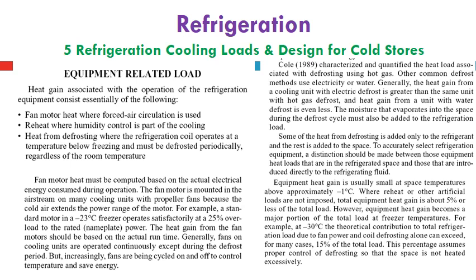However, equipment heat gain becomes a major portion of the total load at freezer temperature. For example, at -30 degrees Celsius, the theoretical contribution to the total refrigeration load due to fan power and coil defrosting alone can exceed, in many cases, 15% of the total cooling load. This percentage assumes proper control of defrosting so that the space is not heated excessively.